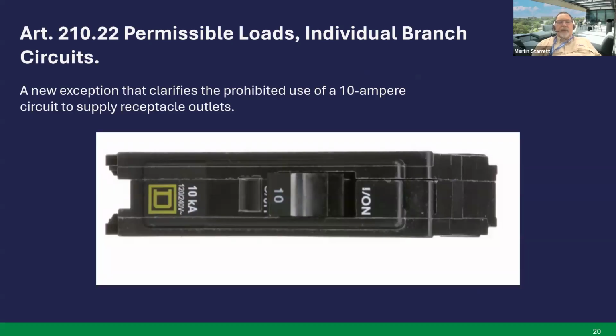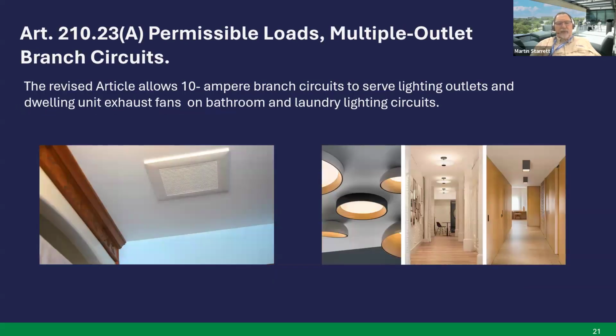Article 210.22, permissible loads, individual branch circuits. In 2020, they started adding this 10 amp branch circuit. In this particular article, they did add a new exception that clarifies the prohibited use of a 10 amp circuit to supply receptacle outlets. In 2023, they had it, but now in 2026, they've removed it. Next slide.